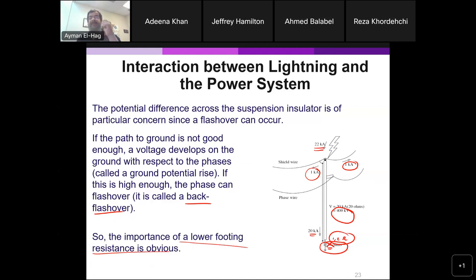So the problem has two sides. One side is the reflected wave: if the foot resistance is higher than the surge impedance, then you will have a positive reflected wave. This will be added, so it's not just the 20 kiloamps, but we will have even more, or the 400 kilovolts. Second, also, is the voltage that is basically developed, as we have seen here.